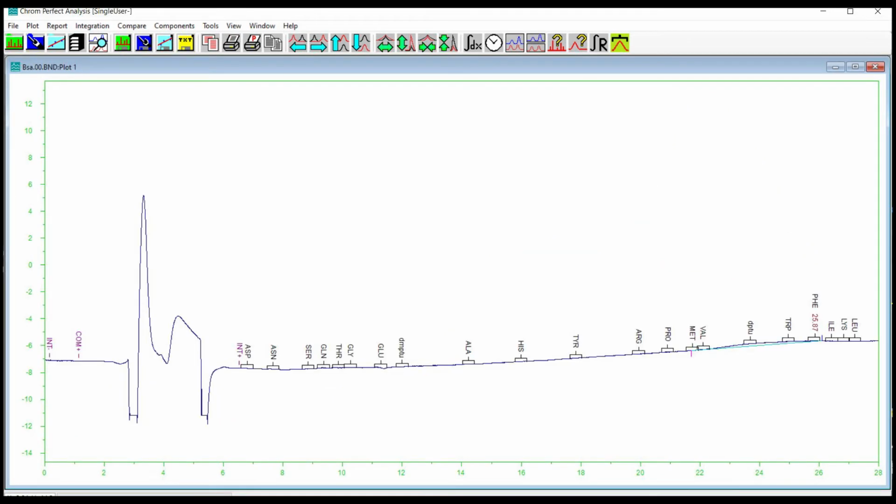The term drift refers to any slow variation in the chromatogram that occurs on a time scale larger than the peak width. There is no clear-cut boundary between noise and drift. The contributors to noise listed above can also cause drift. Other sources of drift include changes in ambient temperature and loss of a portion of the stationary phase at high column temperatures, column bleed. Drift seldom causes analytical problems and, except when caused by column bleed, is easily reduced by allowing sufficient time for the chromatograph to stabilize.